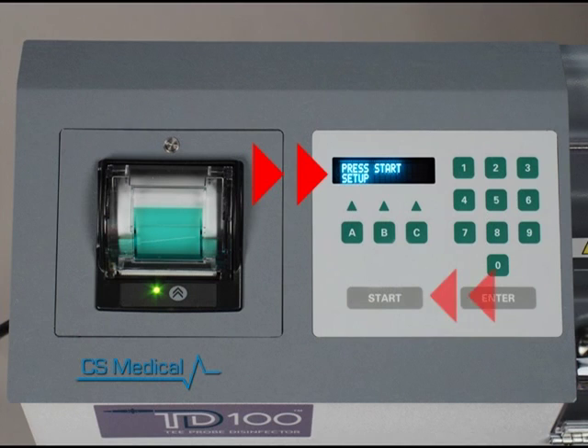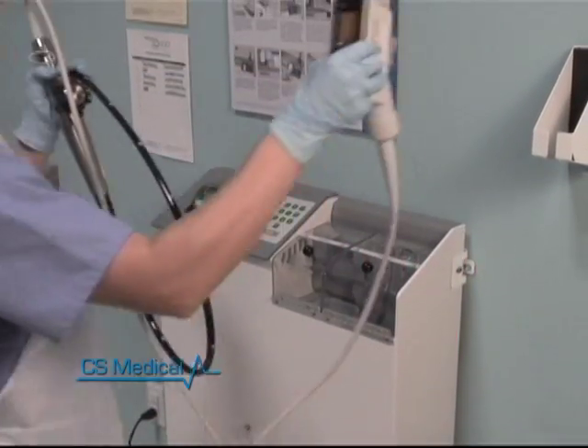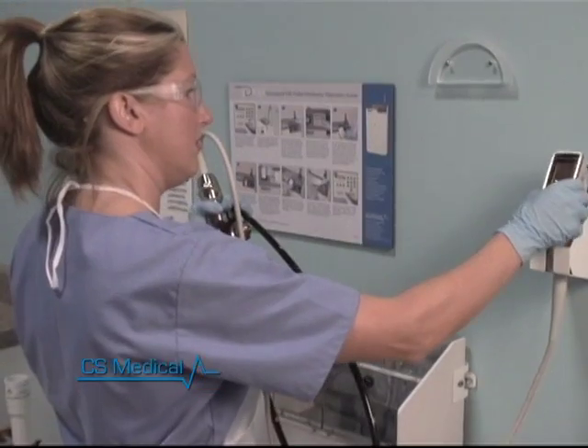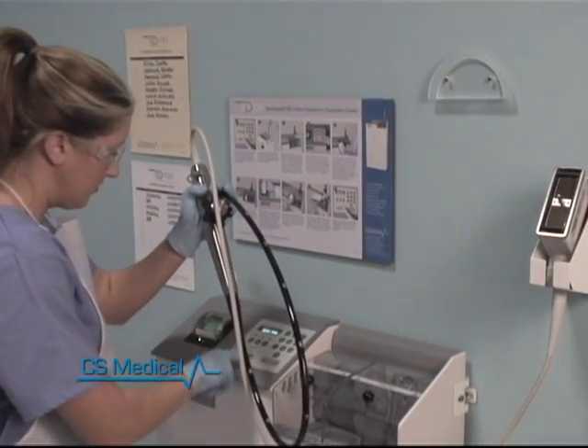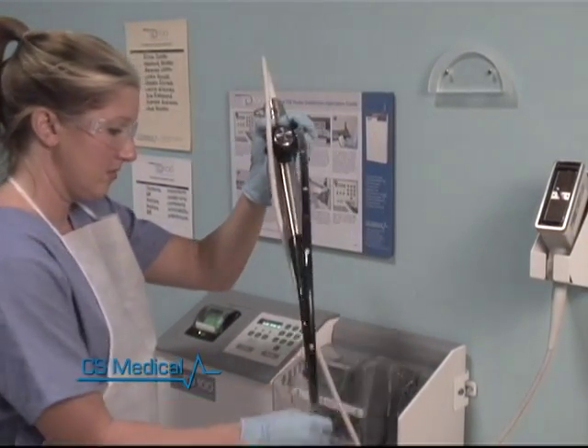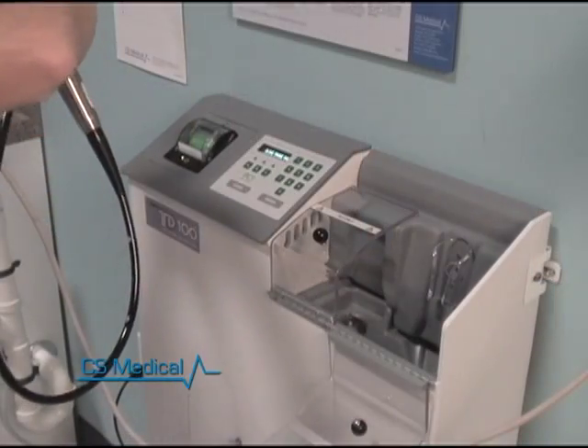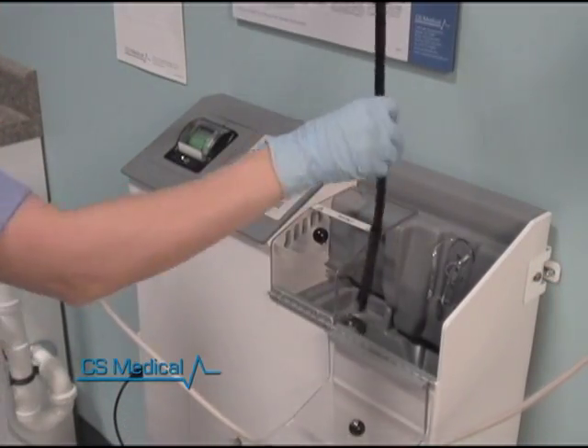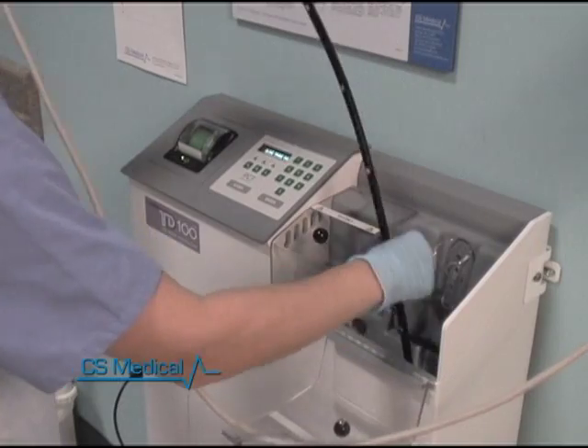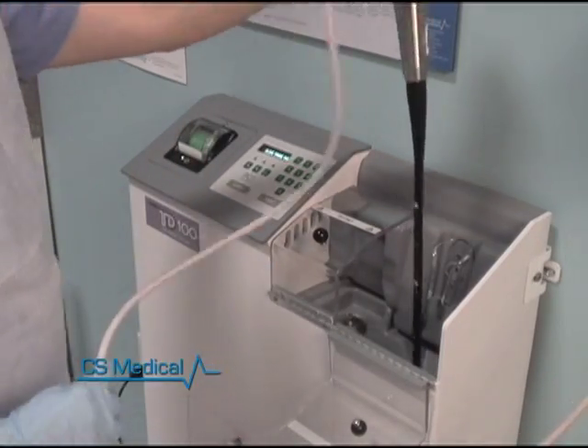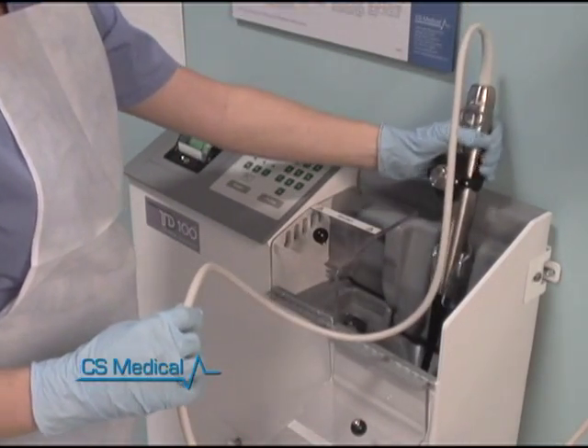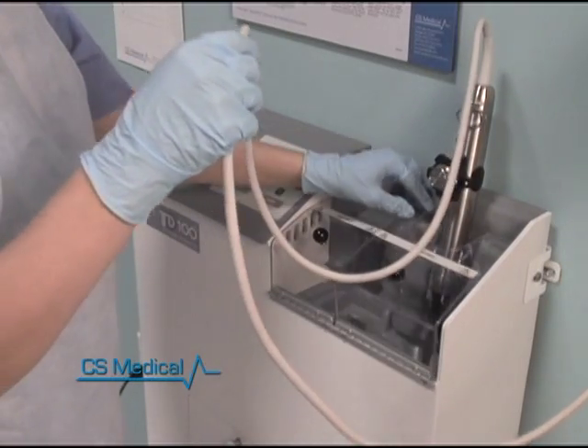Press the Start button and follow the prompts on the LCD screen. You will first be prompted to place your TEE probe into the TD100. Open the hinge door labeled Probe Only. Take the distal tip of the probe and begin to feed it down into the tube located in the reservoir. The handset of the TEE probe should fit easily into the cradle directly above the reservoir tube.